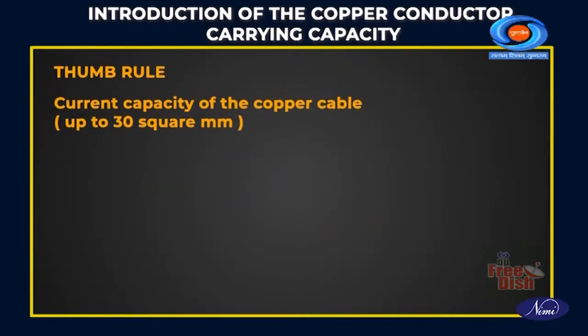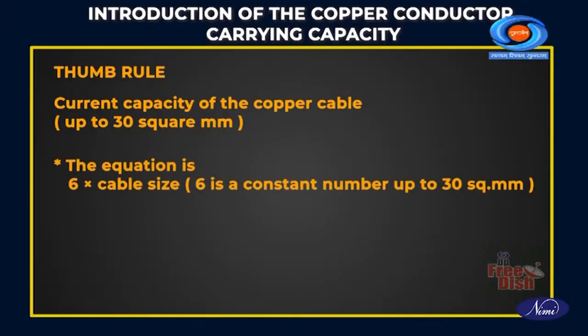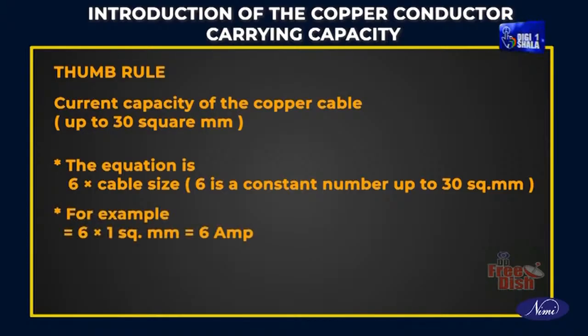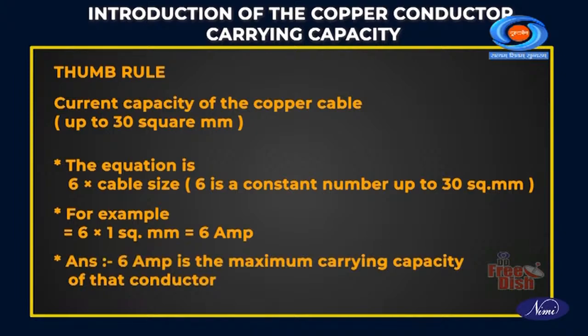Now, we will see a small calculation for the current capacity of copper cable up to 30 square mm. The equation is 6 into cable size. For example, 6 multiplied by 1 square mm is equal to 6 amperes. The 6 amperes is the maximum carrying capacity of that conductor.